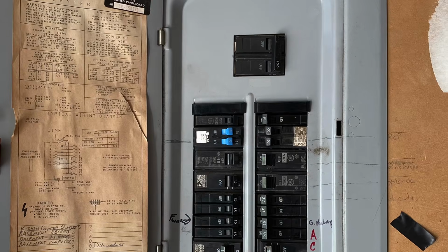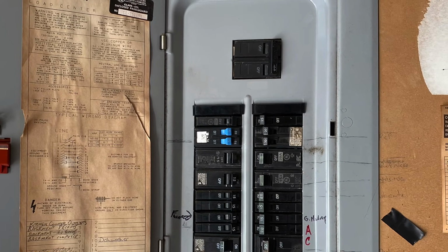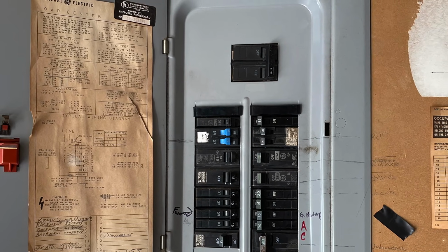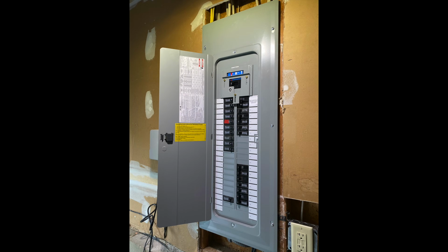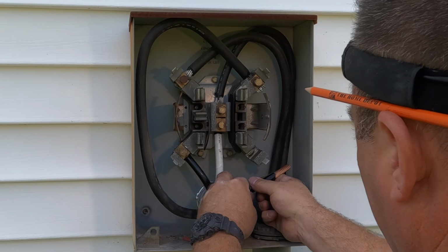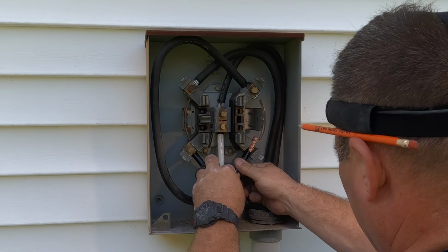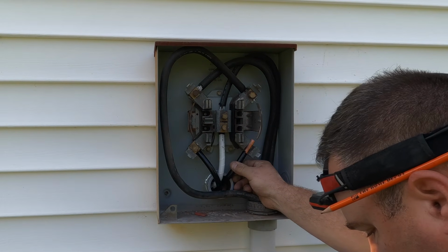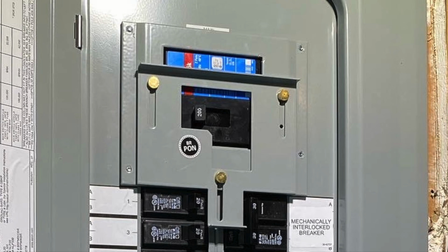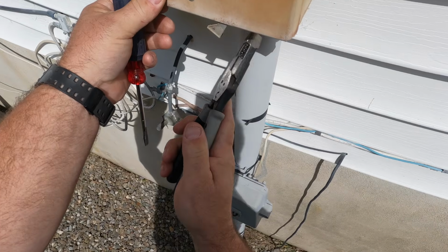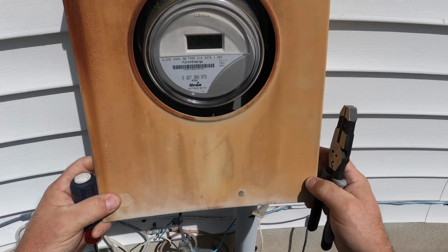In this video today we'll be removing this 100 amp main breaker panel with 20 circuits, and we'll be upgrading to a 200 amp panel with 40 circuits. We'll also be updating the service entrance conductors from the meter to the main breaker panel, and then at the end we're going to install a manual transfer interlock switch in this panel, and then we'll install portable generator wiring for a portable generator connection.